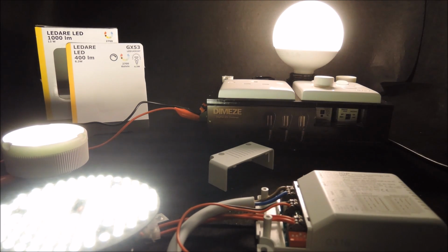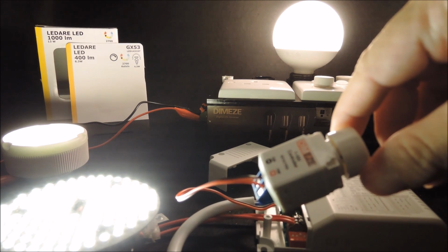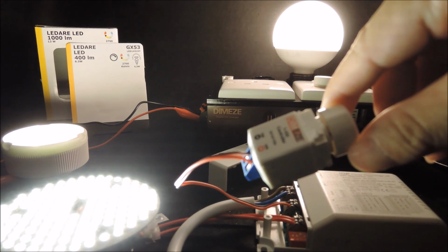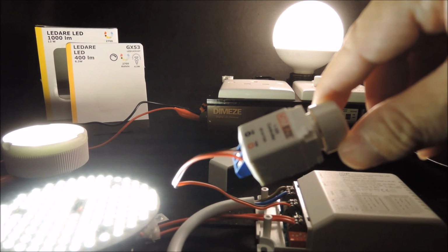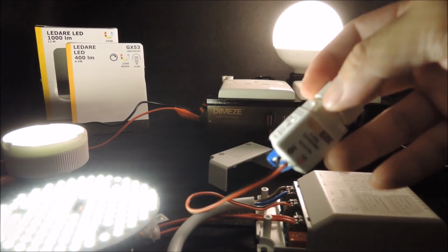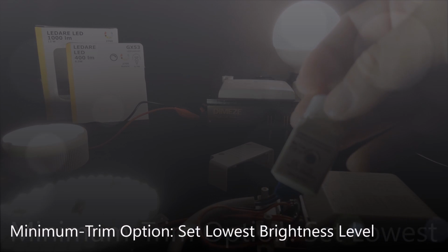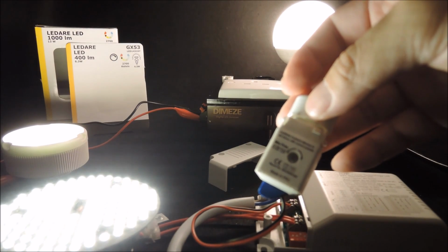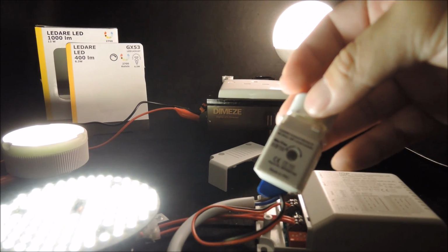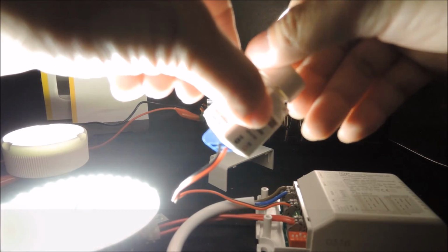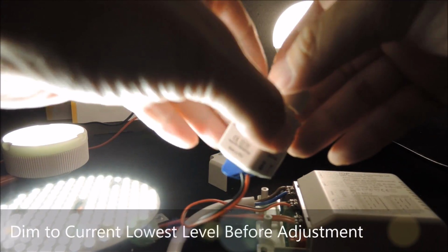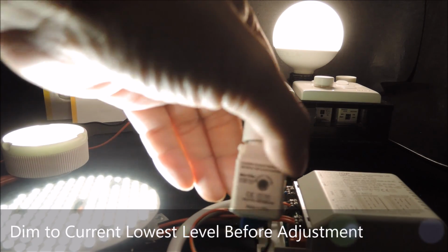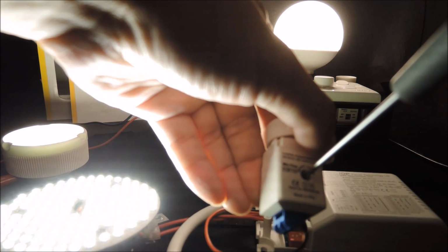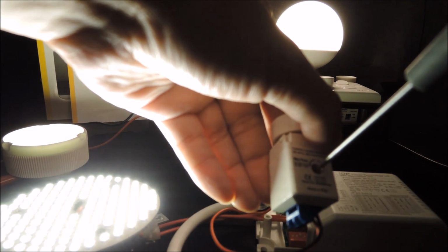The 1 to 10 volt controller provides the brightness control in scale from approximately 10% to 100% or equivalent to full brightness. The minimum trim option available with our DZ1G110 helps further adjustment of the lowest brightness level. To set it, we first dim the light to the current lowest level, and then we can use a screwdriver to manipulate the level like this.